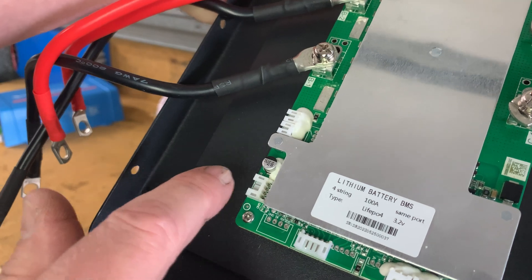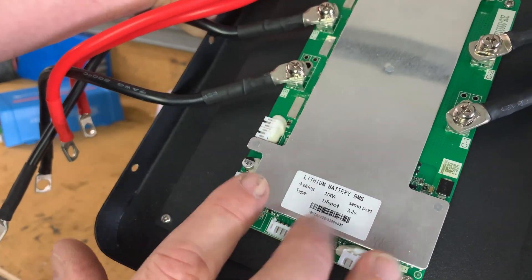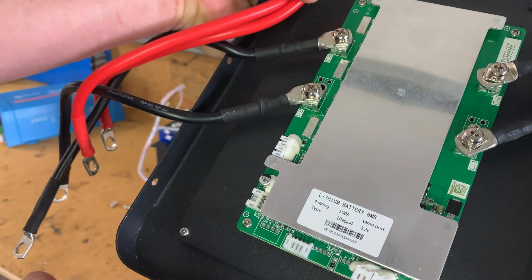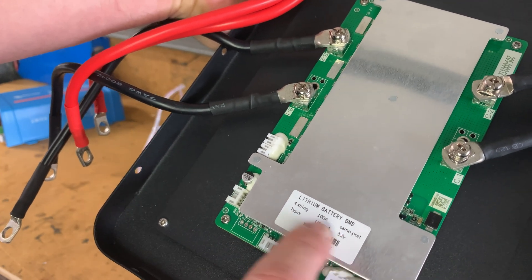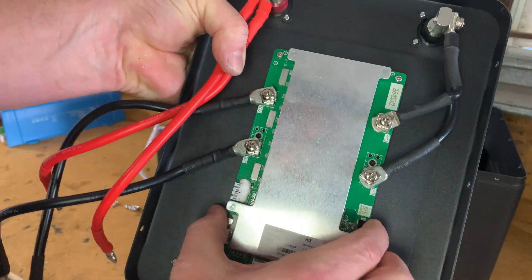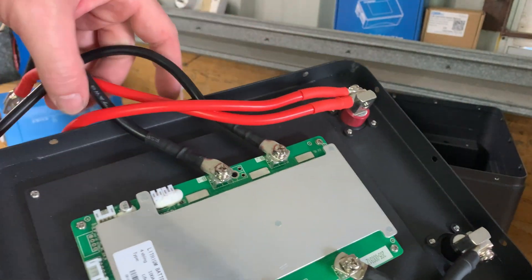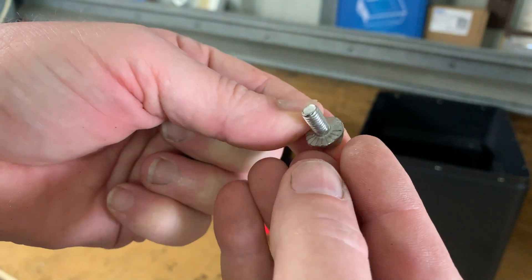There's no model number really on the BMS and it doesn't come with a Bluetooth adapter — they do sell a Bluetooth model. I would buy the Bluetooth model because I like seeing what my BMS is doing. The label says: lithium battery, four string, 100 amp, same port type, LiFePO4, 3.2 volts, with a serial number underneath. All the screws are mounted very firmly. The terminal bolts have a serrated component so they are not going to back off easily.